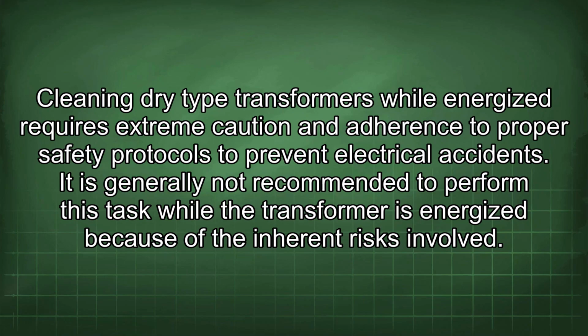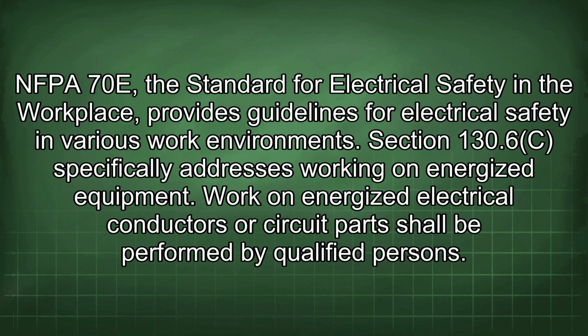Cleaning dry-type transformers while energized requires extreme caution and adherence to proper safety protocols to prevent electrical accidents. It is generally not recommended to perform this task while the transformer is energized because of the inherent risks involved. NFPA 70E, the standard for electrical safety in the workplace, provides guidelines for electrical safety in various work environments.